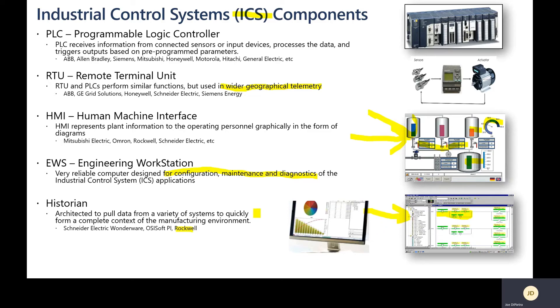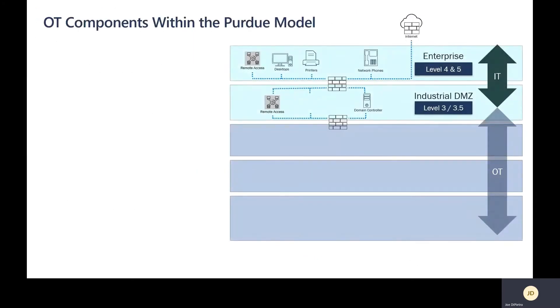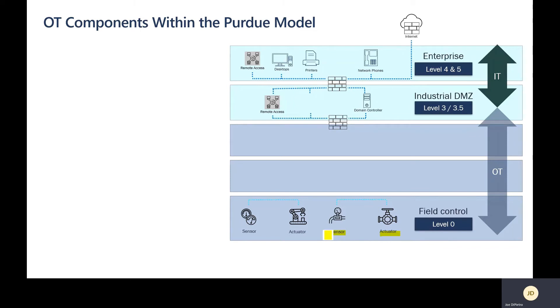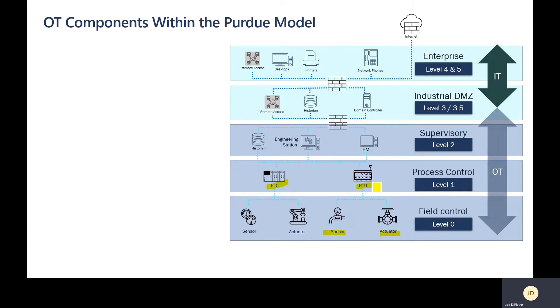These are the different components of the OT network. Now let's place these control systems in the right layer within the Purdue model. At level zero, you have actuators and sensors — the field control components. At the process layer (level one), this is where PLCs and RTUs reside. At the supervisory layer (level two), you have your HMI, engineering workstation, and historian. This provides different visibility depending on which layer of the OT network you're in.